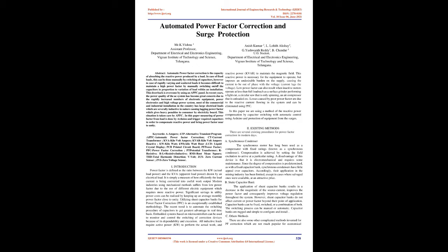In recent years, the power quality of the AC system has become a great concern due to the rapidly increased numbers of electronic equipment, power electronics and high voltage power systems. Low power factor can also result when inductive motors operate at less than full load, such as a surface grinder performing a light cut, a circular saw that is only spinning, an air compressor that is unloaded, etc. Most of the commercial and industrial installations in the country have large electrical loads which are severely inductive in nature, causing a lagging power factor, which gives heavy penalties to the consumer by the electricity board. Losses caused by poor power factor are due to the reactive current flowing in the system and can be eliminated using PFC.